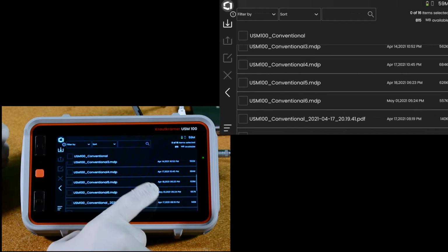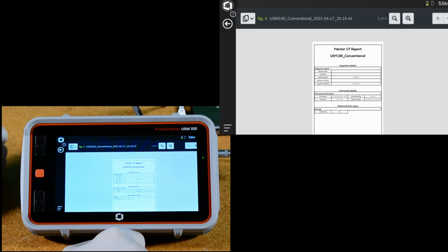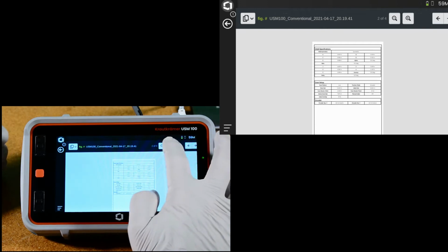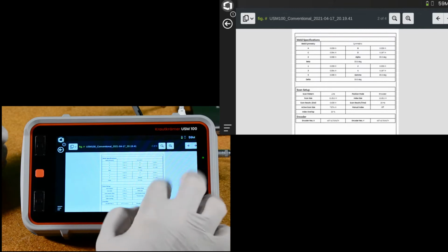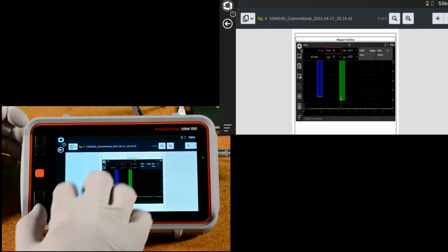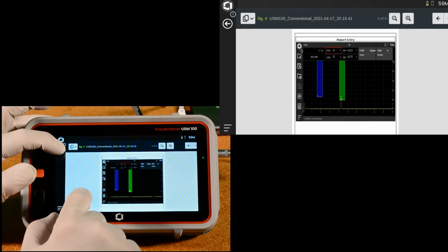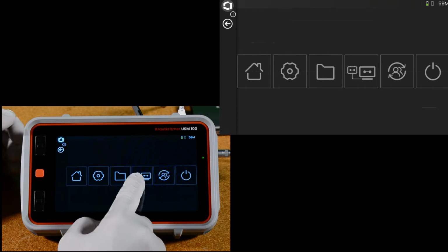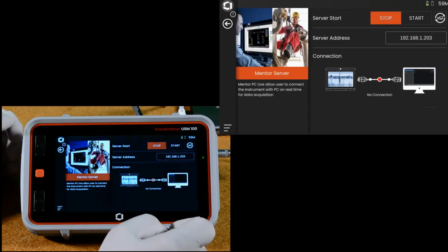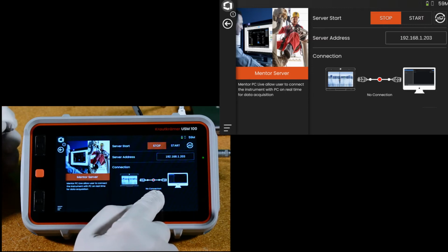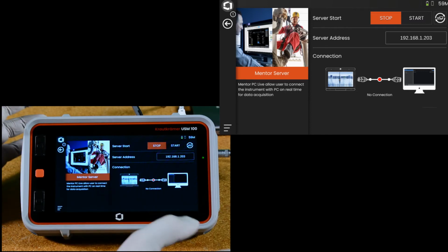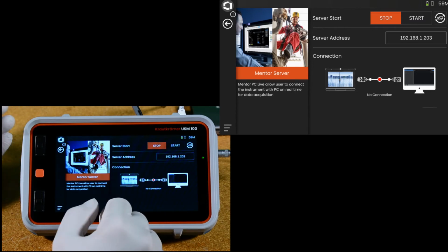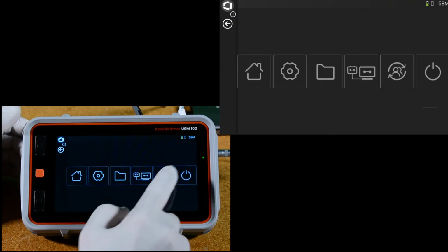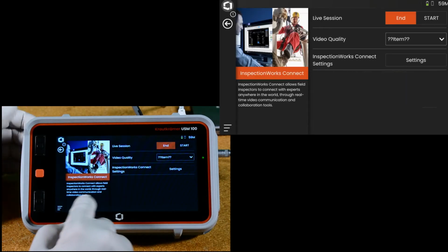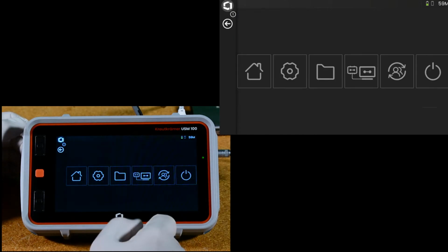If I do that same action on a report file, I get a PDF viewer. I can go forward and backwards on pages, I can zoom in, I can scroll up and down, I can have a look at my report, and each report includes at least one screenshot. So if we go back to our settings panel, the next icon is our setup for USM 100 PC Live. This is PC software that can link through Ethernet. That basically provides all the functionality on the instrument on the PC, with the instrument being the front end for ultrasonics. We have Inspection Works Connect, long distance internet connectivity for others, and a shutdown icon.